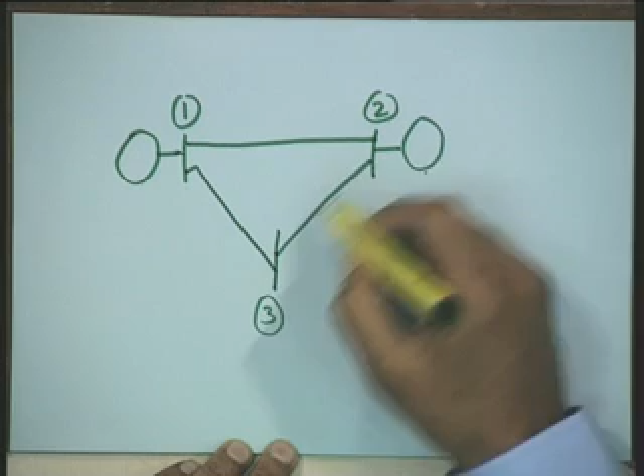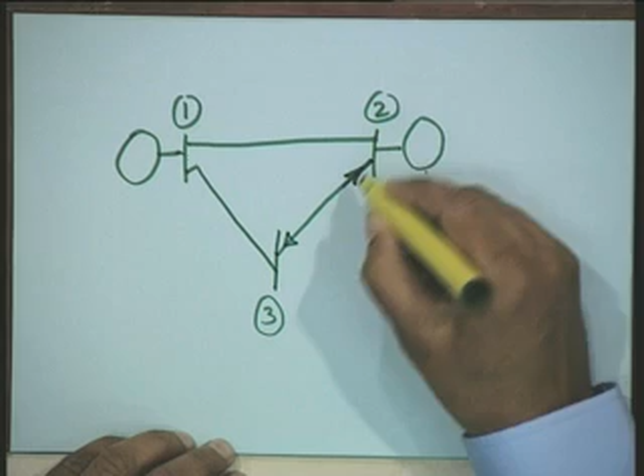One simple way is that I obtain the model considering this post-fault or post-tripping situation. Another way of simulating will be that you look at, before the occurrence of the fault, what was the power which was flowing on this line. Let us say I am just showing here, of course I am putting opposite arrows, the power entering this bus I call P2, and the power entering at this bus is called P3 because of this line connection. For example, if you consider a lossless line, if P2 is say 50 megawatt, P3 will be minus 50 megawatt.